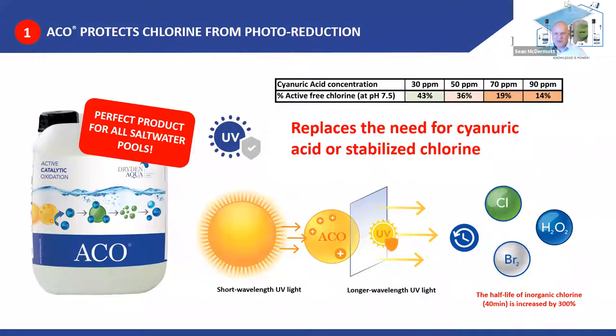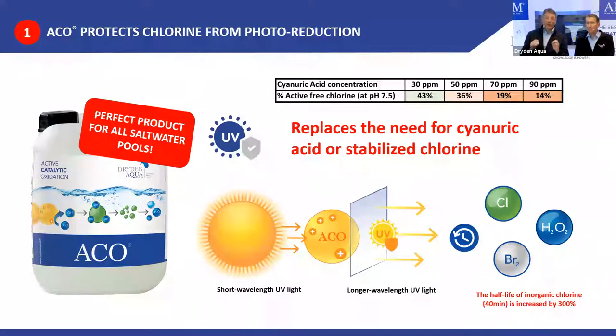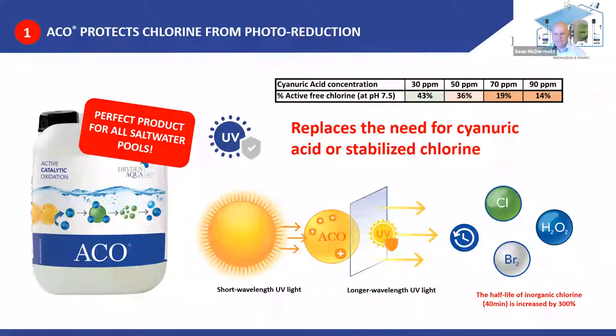With ACO, we can achieve a similar level of UV protection, but 100% of the chlorine in the water is available to disinfect — assuming proper pH and other water conditions. In Switzerland, Germany, Austria, and many Eastern European countries, cyanuric acid is actually forbidden in public pools. They operate pools between 0.3 to 0.6 ppm free chlorine. Seven ppm is a number they don't even know how to write.